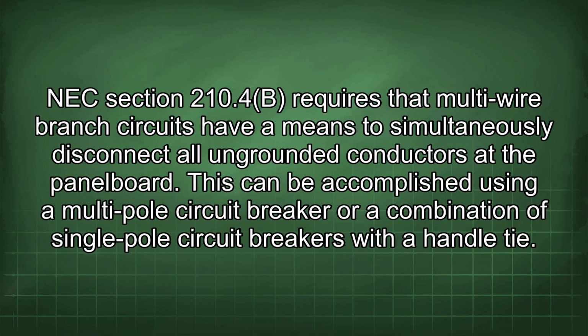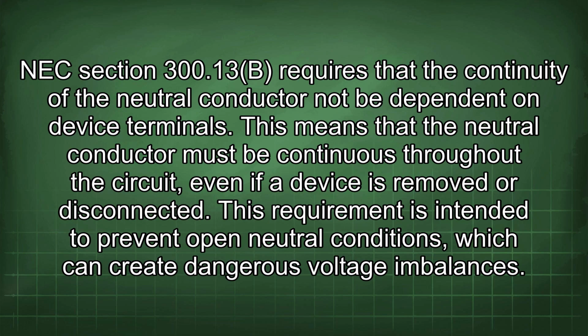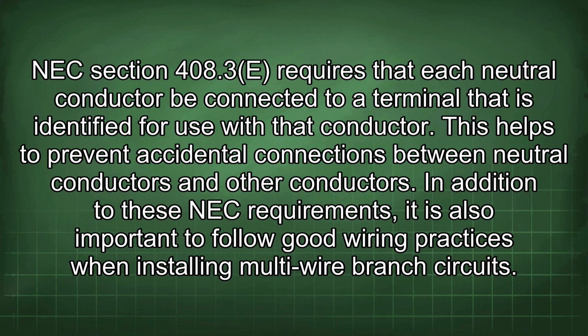NEC Section 210.4(B) requires that multi-wire branch circuits have a means to simultaneously disconnect all ungrounded conductors at the panel board. This can be accomplished using a multi-pole circuit breaker or a combination of single-pole circuit breakers with a handle tie. NEC Section 300.13(B) requires that the continuity of the neutral conductor not be dependent on device terminals. This means that the neutral conductor must be continuous throughout the circuit, even if a device is removed or disconnected. This requirement is intended to prevent open neutral conditions, which can create dangerous voltage imbalances. NEC Section 408.3 requires that each neutral conductor be connected to a terminal that is identified for use with that conductor. This helps to prevent accidental connections between neutral conductors and other conductors.